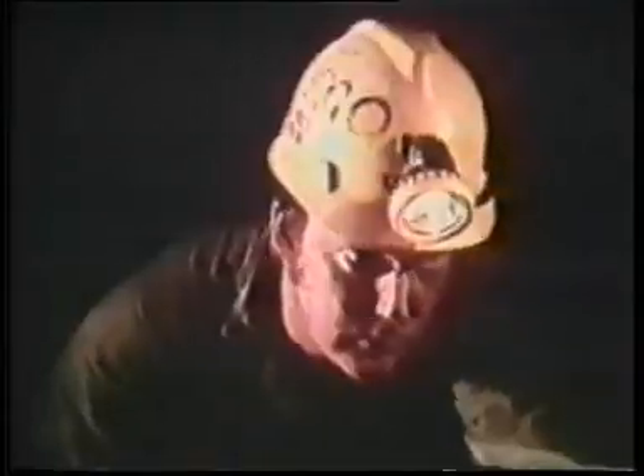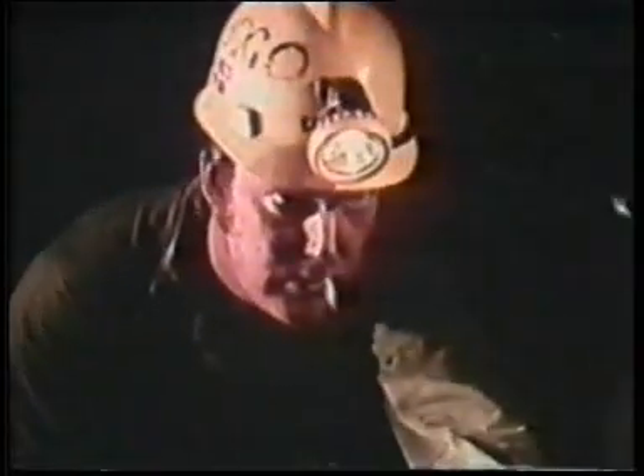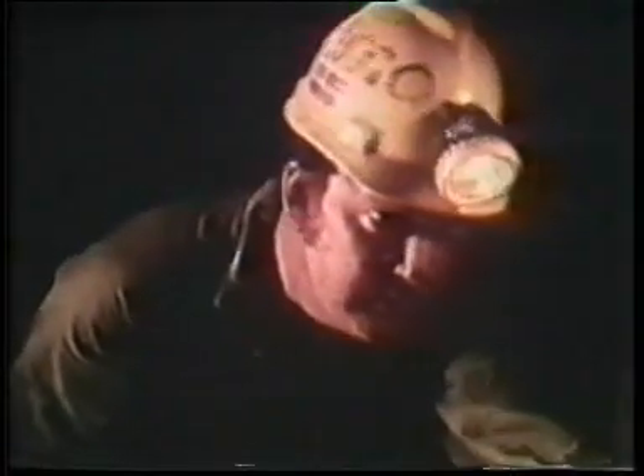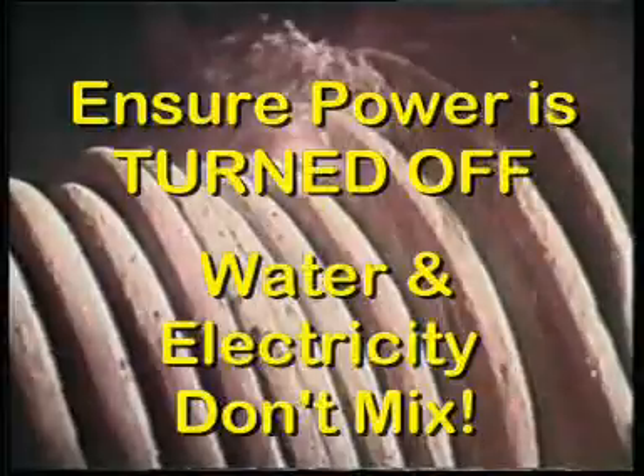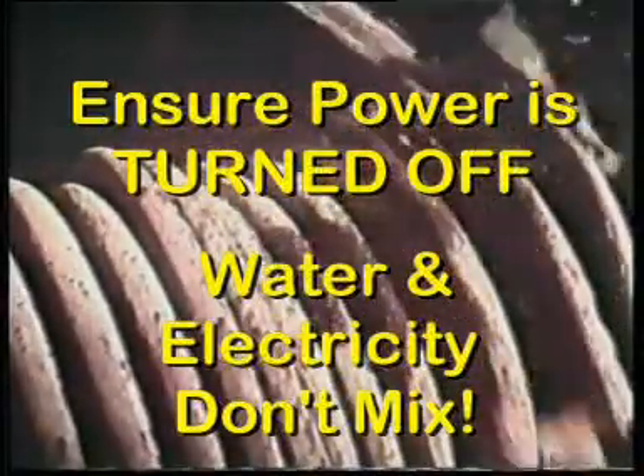As soon as oxygen reaches the hot-sealed inner layers of cable, there is imminent danger of ignition. Experience proves that a normal fire extinguisher will dampen down a fire by sealing off the cable from oxygen, but only temporarily. It has little effect in reducing the heat of the inner layers, which will again ignite. Water alone will effectively cool the cable to a level where the fire will be extinguished and will not restart.